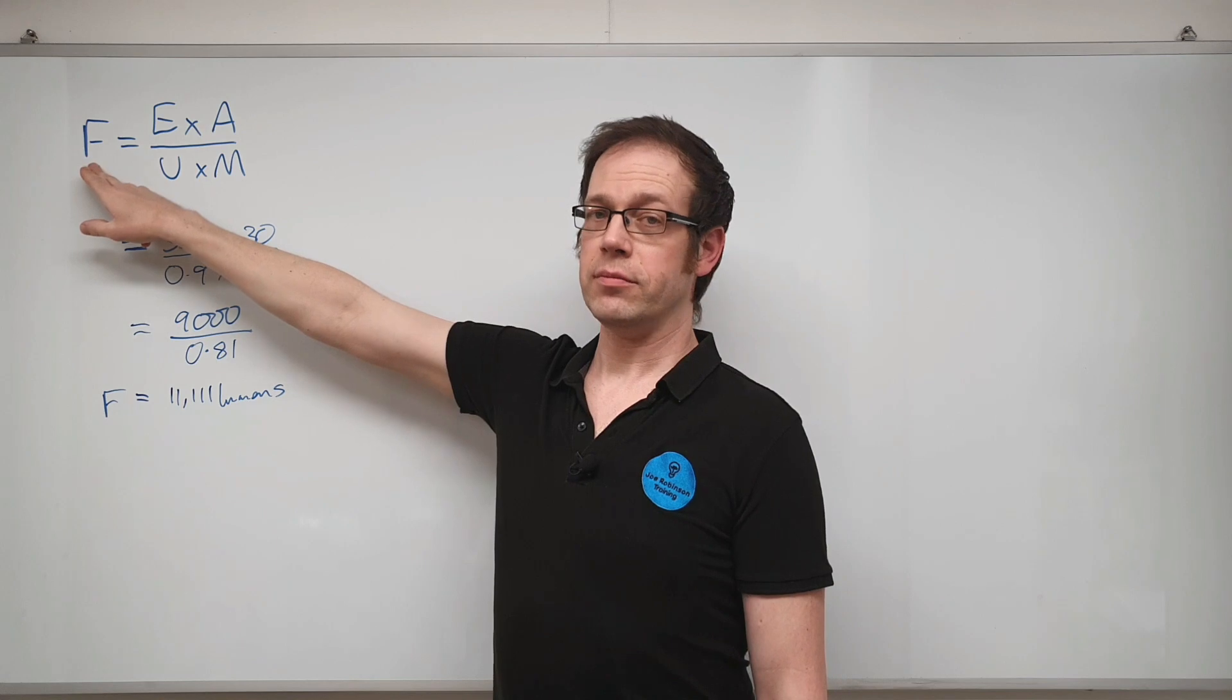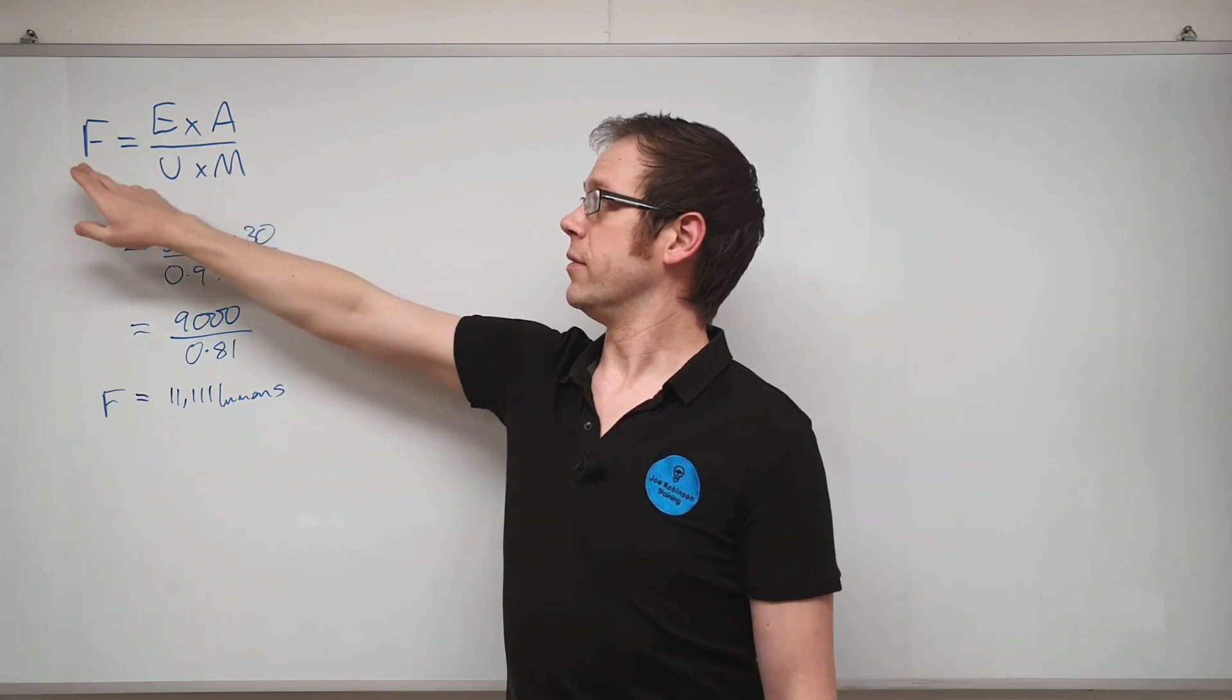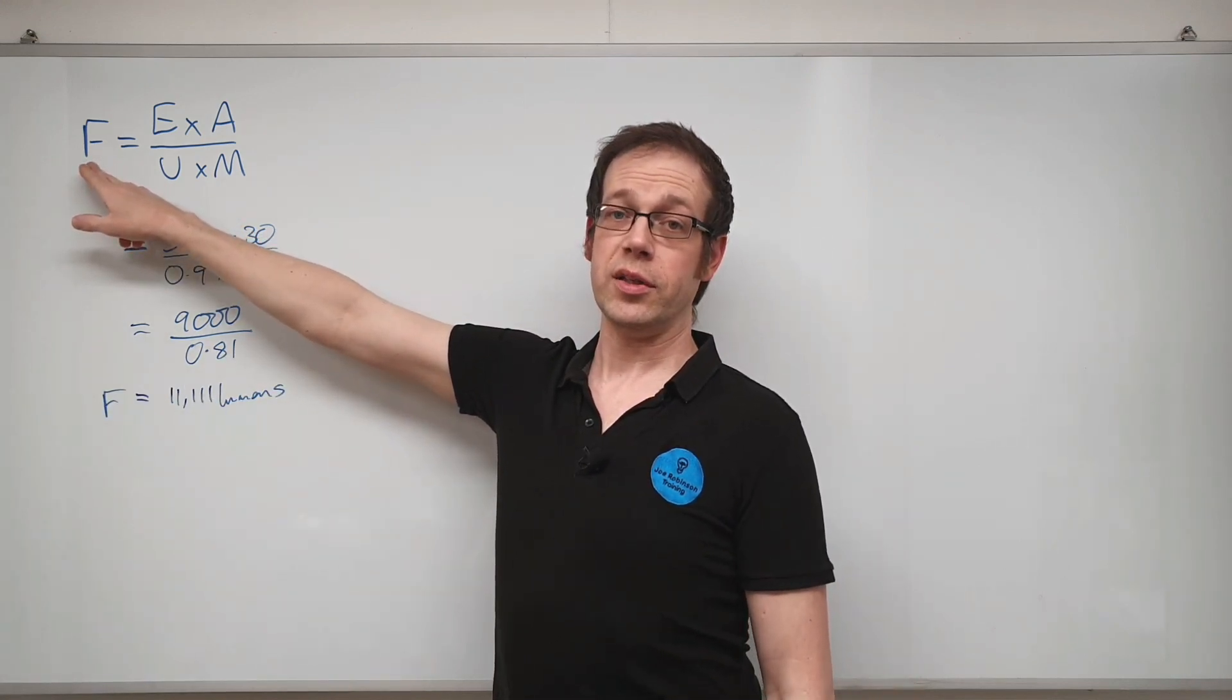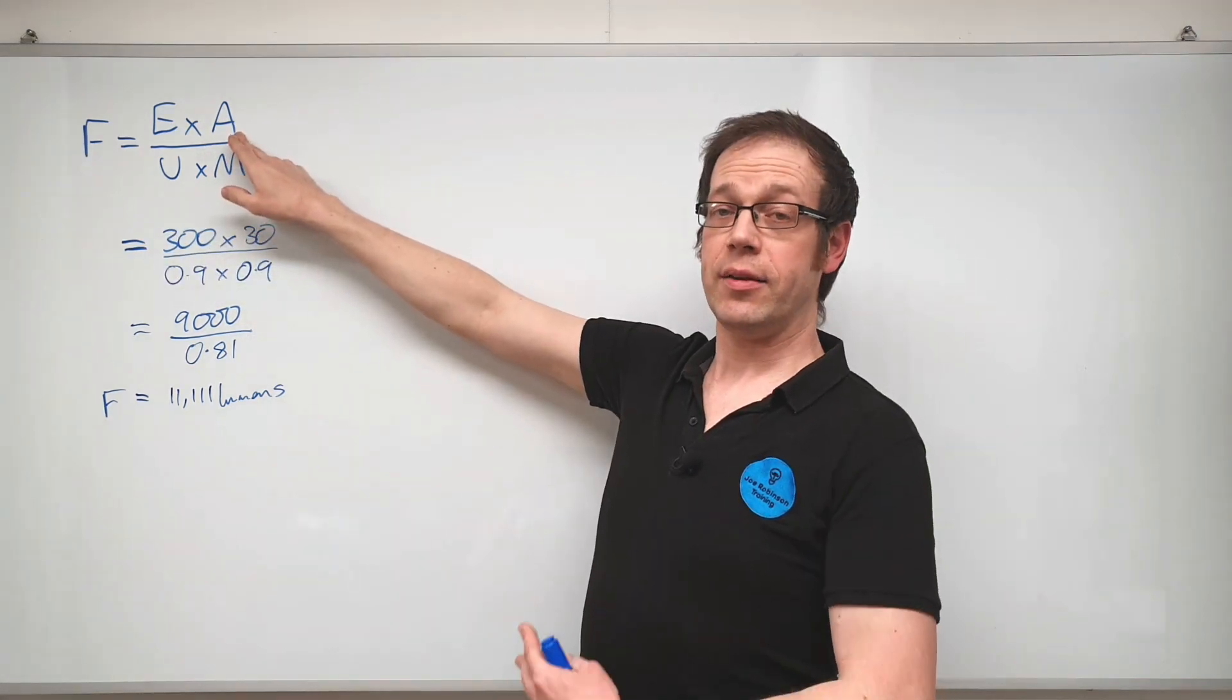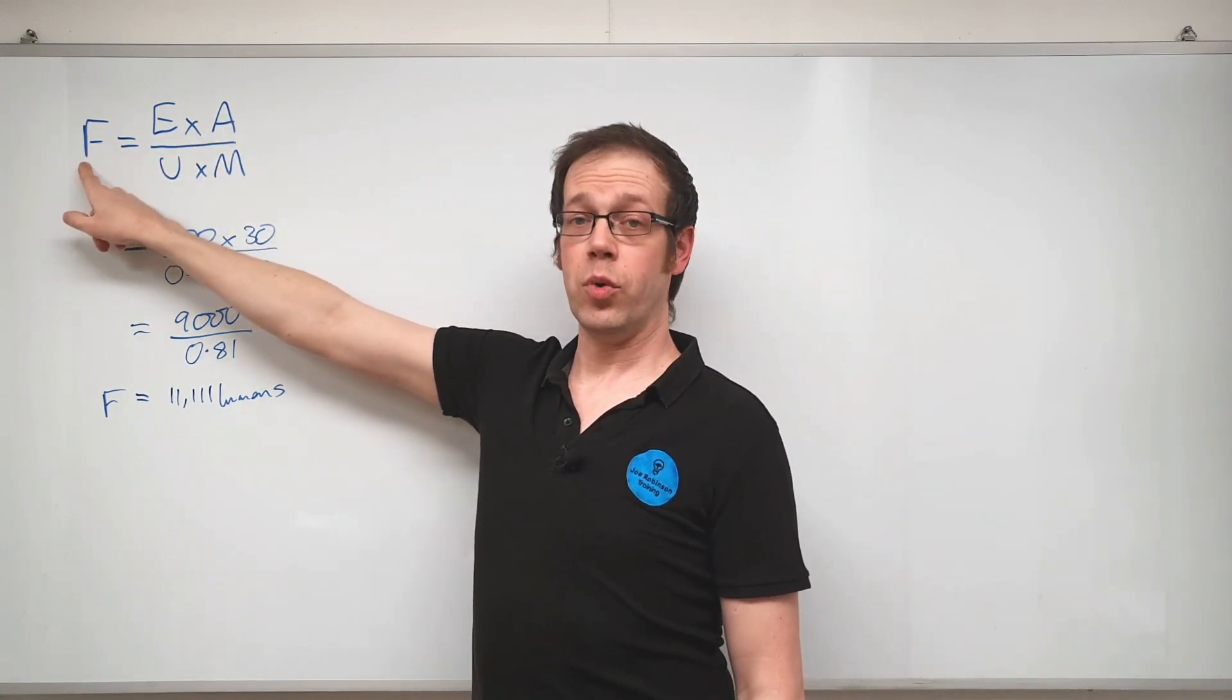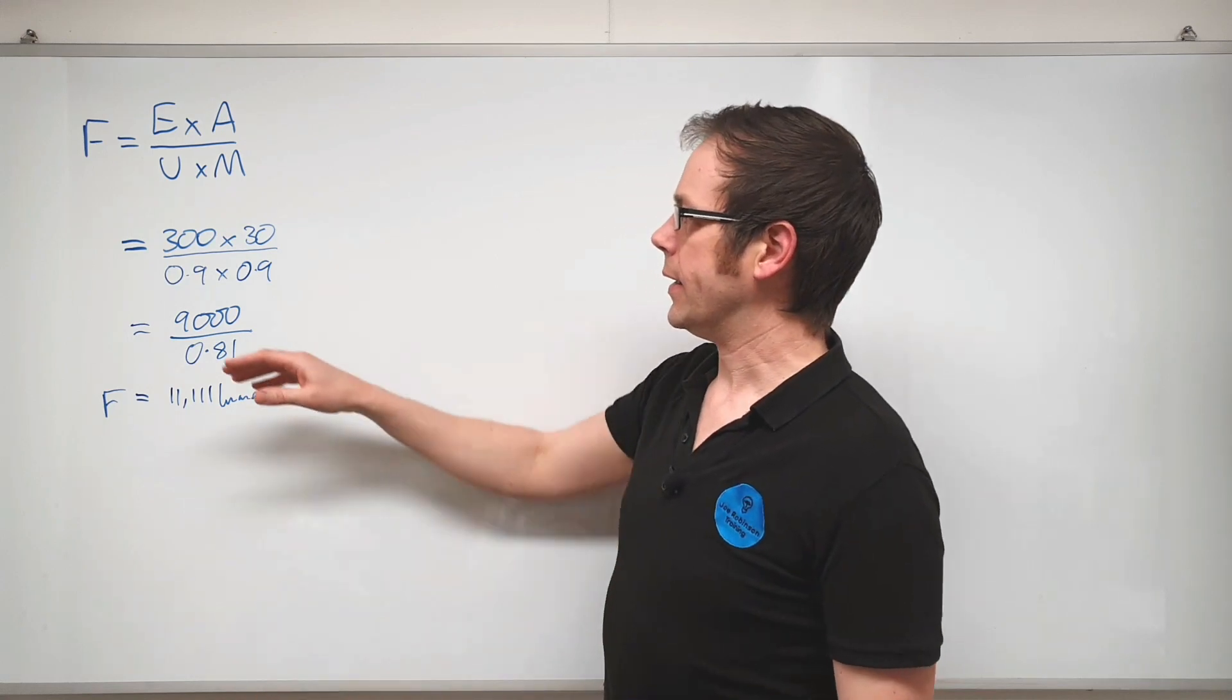If we make this number bigger, what's going to happen to this number? If we make E bigger, what happens here? Well because this is on the top of the calculation, on top of the division, if we make this number bigger, this number gets bigger—which makes sense, doesn't it? If we want the surface to be more brightly lit, then we need to increase the amount of light output that the light sources have. Again, if we make this number bigger, if we make the room area bigger, then we're going to increase this number here, which means that again increasing the area means that we need more lumens.